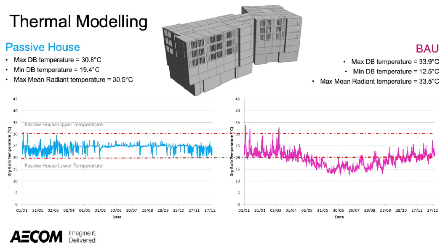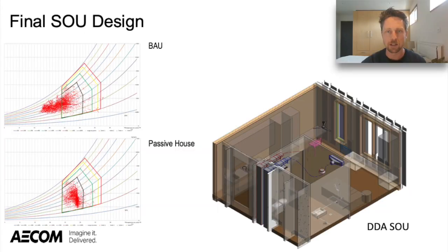The final design for each of the spaces is then very cut back: air is supplied out into the bedrooms and then extracted back in from the bathrooms. That same system has mechanical dampers which control the amount of air being distributed to the space. Low-level air is supplied into the spaces at all times, but the system can operate as a boost when the bathroom is in use, or when the whole building is trying to purge heat.